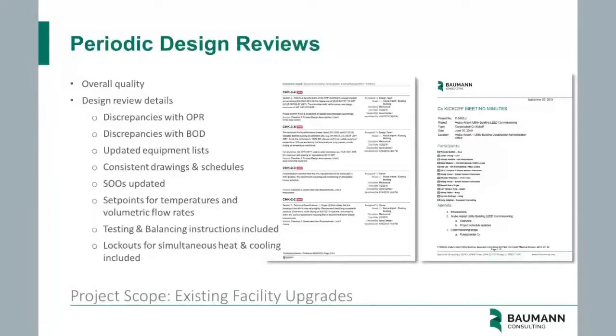Any equipment list updates that were not tracked, any inconsistent drawings or schedules, making sure that the sequence of operations were updated, making sure that set points and volumetric flow rates were included, whatever testing and balancing instructions were going to be required, and lockouts for heating and cooling, simultaneous heating and cooling.